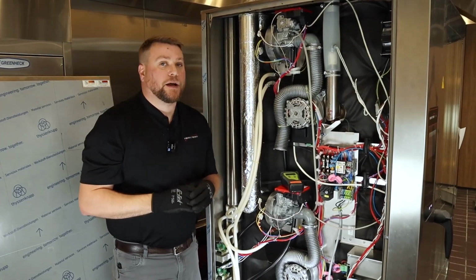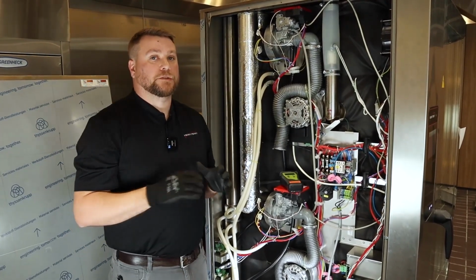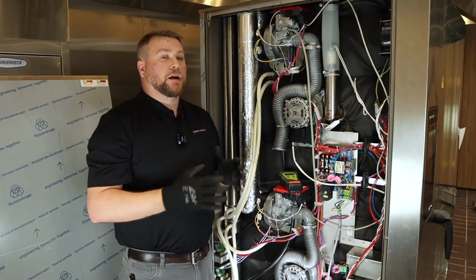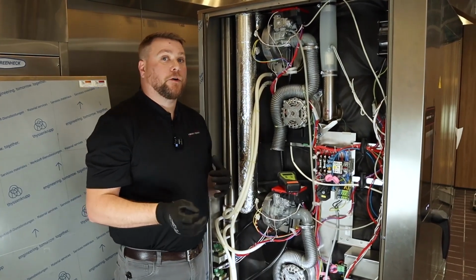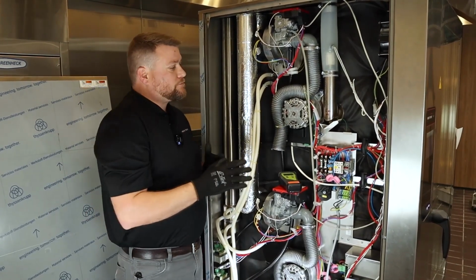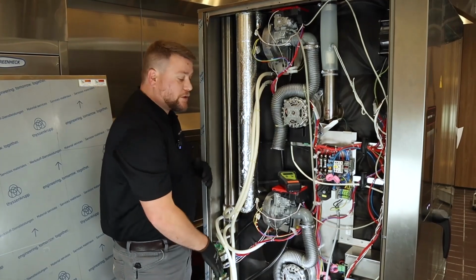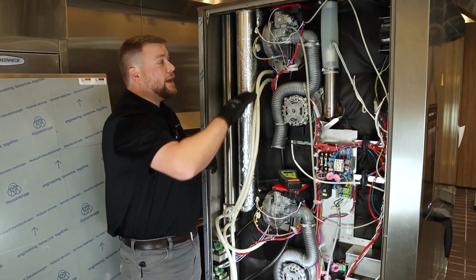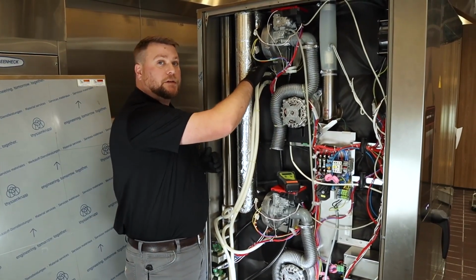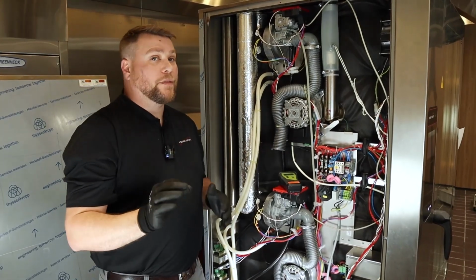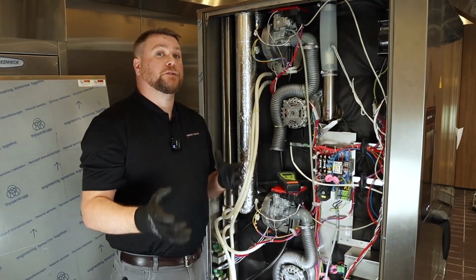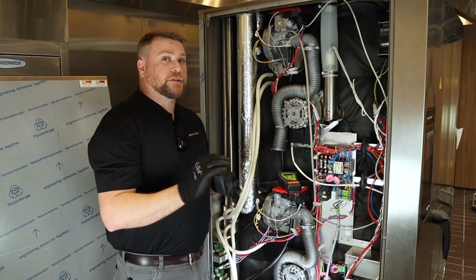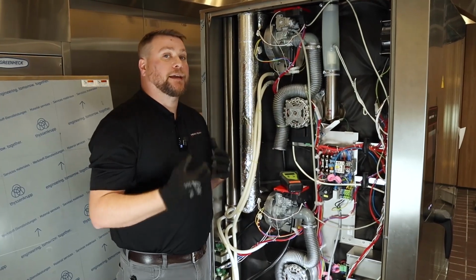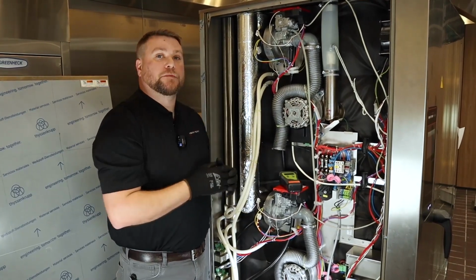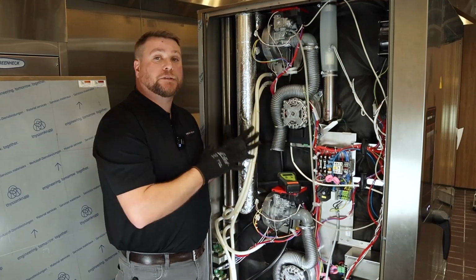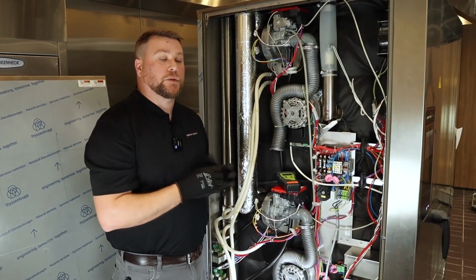So now let's talk a little bit when it comes to troubleshooting some gas-related issues. A couple of the biggest components involved with gas-related issues is going to be our glow electrodes, maybe our transformer, and then also our flame sensor. Those are some of the big culprits, but one thing we need to keep in mind is also gas pressure. And not just pressure, but more specifically, gas volume, especially when it comes to these larger units and especially in stores that have multiple units.